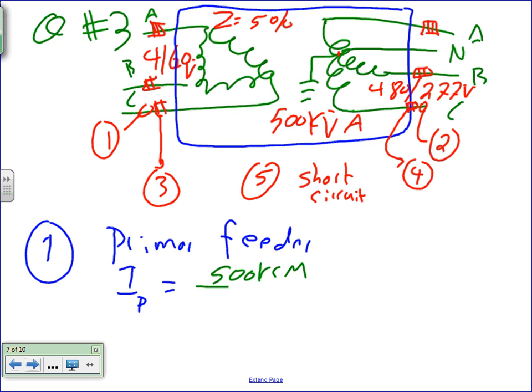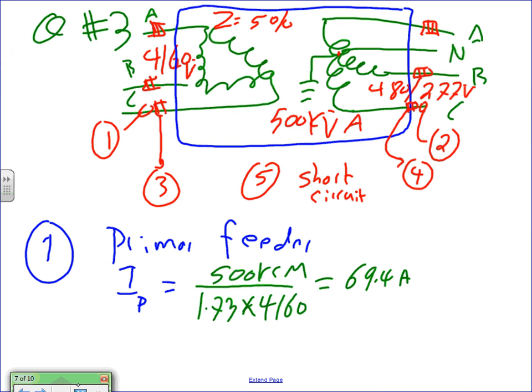So take this divided by 1.73 times 4160. That will give you a healthy 69.4 amps. Now, since this is a medium voltage, guys, I would size directly based on 69.4. If you want to multiply it by 1.25, be my guest, and take it all the way to table 310.60, I believe.